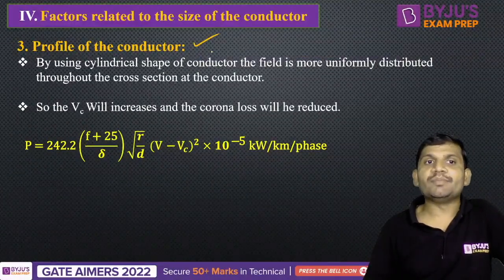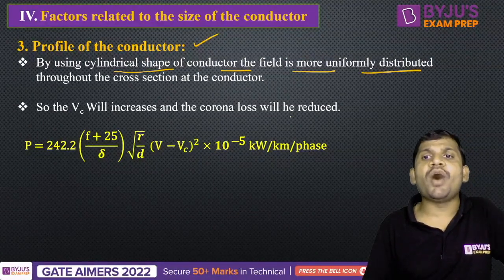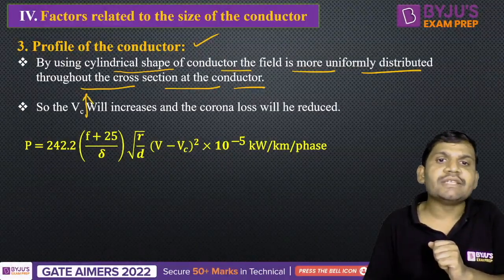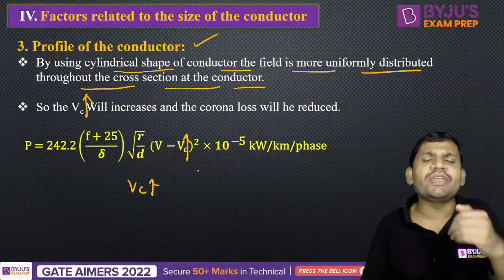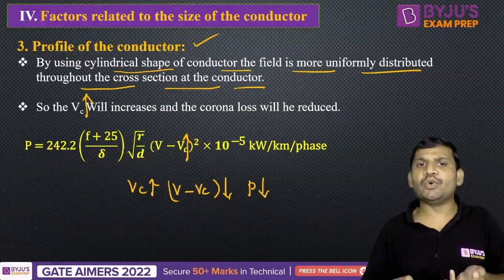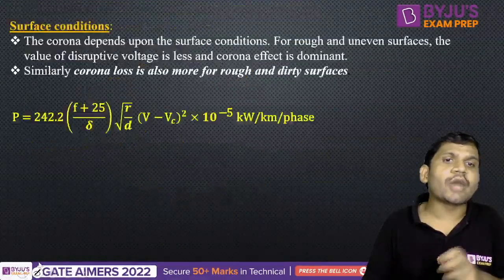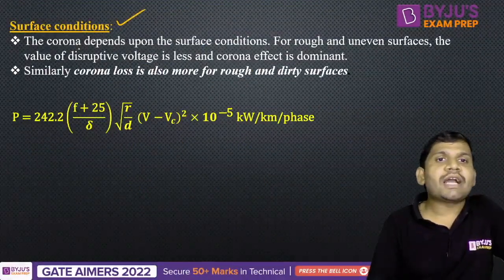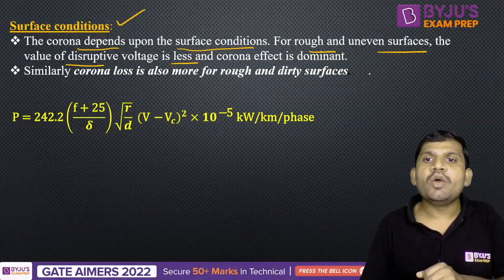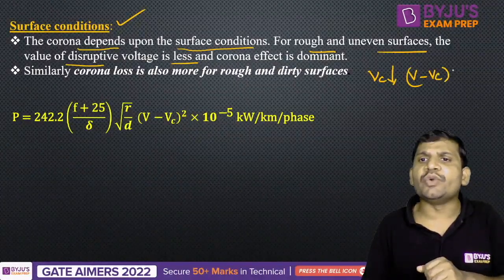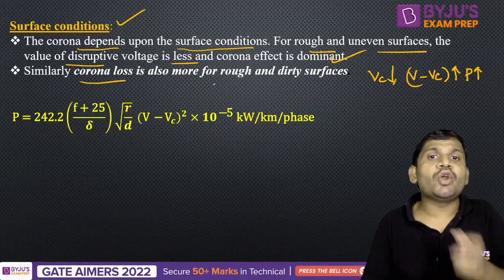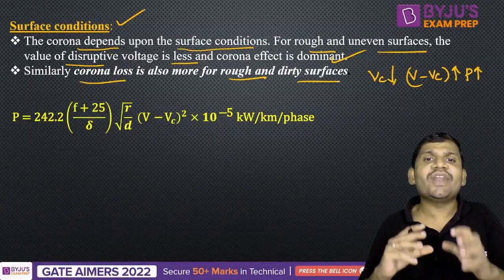One more important factor is the profile of the conductor. If you use a cylindrical shape of the conductor, the field is more uniformly distributed throughout the cross-section. Once the field is uniformly distributed, Vc will increase. If Vc increases, V minus Vc reduces, and corona loss is reduced. Also, surface conditions matter: for rough and uneven surfaces, the critical disruptive voltage is less, so V minus Vc increases and power loss increases. Corona loss is also more for rough and dirty surfaces.